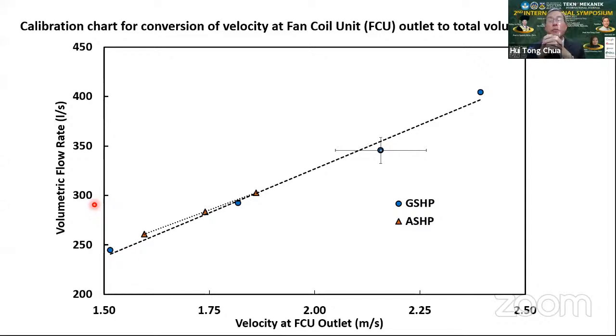But suffice to say, we are very proud to report that the volumetric flow rate we measured at every speed setting of the system was spot on compared with the manufacturer's catalog data to the third significant figure. I'm professionally very proud of that achievement. And the manufacturer, Water Furnace, actually reported the airflow rate at the lower speed setting wrongly. So that was my most gratifying moment, knowing that we got this right, which is the most crucial point for the project.